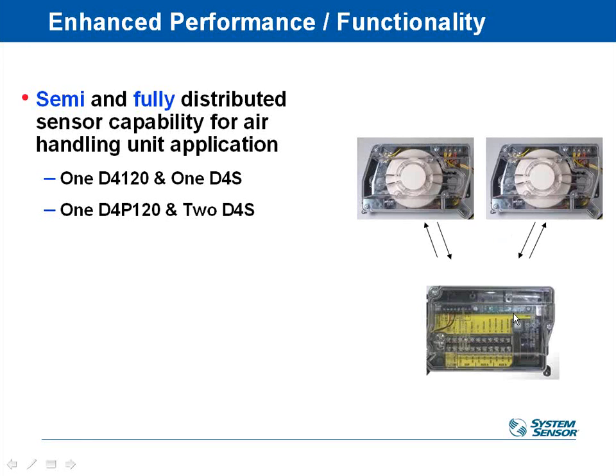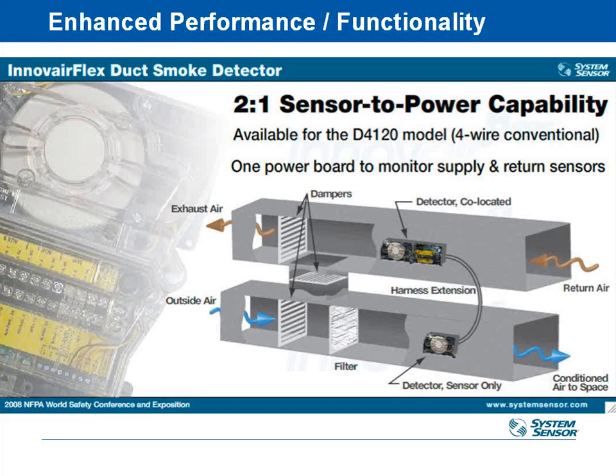The other way to do it is you can not buy a regular detector and you could buy 2 of the heads and buy 1 control board. This would be useful if you want to mount the control board in the rooftop control section instead of out in the duct. So you can have 1 detector in the supply, 1 detector in the return, both of them wired back to the central control panel, which is inside the actual rooftop electrical panel. So you can do it that way as well.